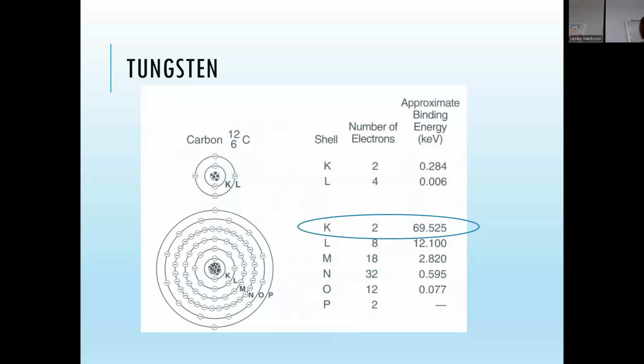Because the more I say it, I was thinking that characteristic could happen on different levels, different shells, but I think perhaps, especially with this, you can only get that high-powered X-ray photon when you have a 70 kVp. So it's a process that needs that power. If it doesn't have that power, then it's not going to create it. And like I said a second ago, that is the power that our machines are set to.